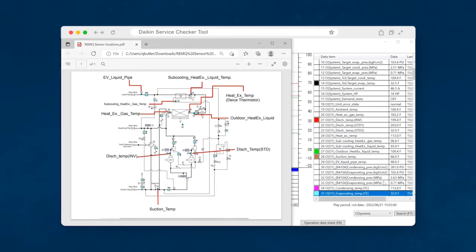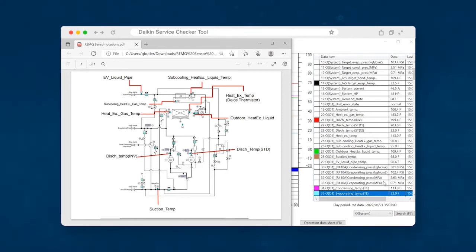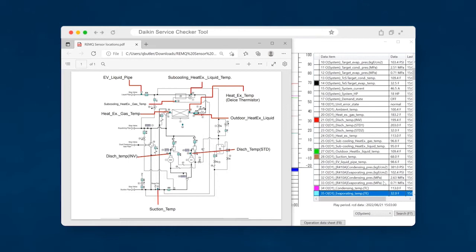So the next step would be to see what our suction superheat looks like. So the suction superheat is calculated in the exact same manner that you would calculate suction superheat on a conventional split system. And so you will take your suction pipe temperature and you'll subtract your evaporator temperature. So let's break out the handy dandy calculator. We've got 68 degrees, and then you subtract 32. So 68 minus 32 gives us 36 degrees.